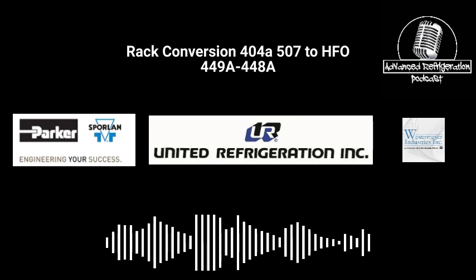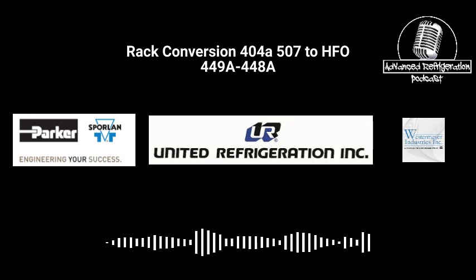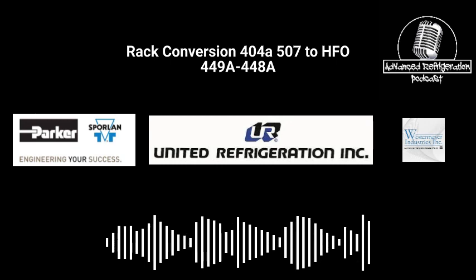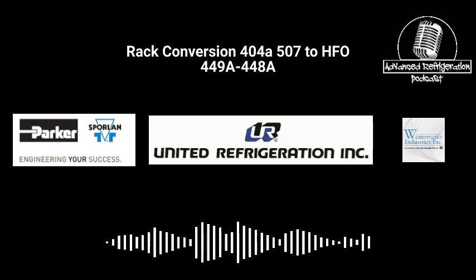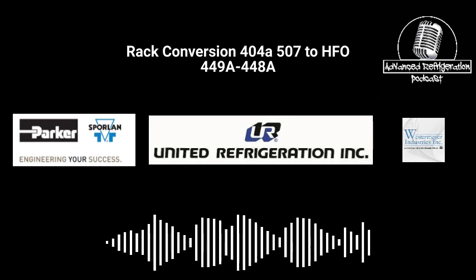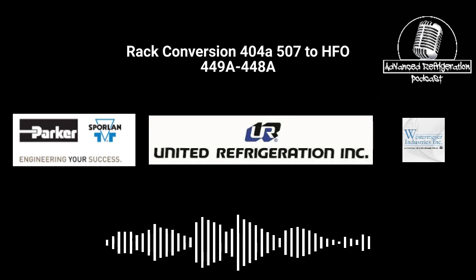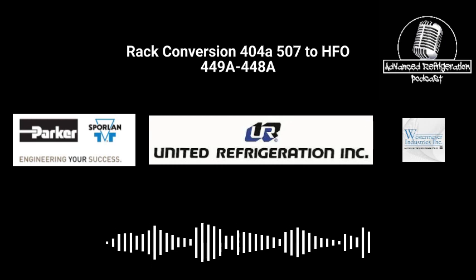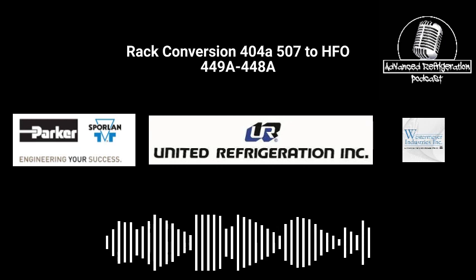As you're doing this, you're getting everything cleaned up, and I leave the store side to the end. So you've got Schraders to do. You don't have to do Schraders, on everybody's spec it's been if they're leaking or not. Me personally, I do the Schraders, especially all of them in the rack. It's cheap insurance, it doesn't take that long. You could have two apprentices knock out a rack or two a day, just go through with core pullers and change all the Schraders, put caps on, paint them blue, so that way you know the cap's been changed and everything's good.